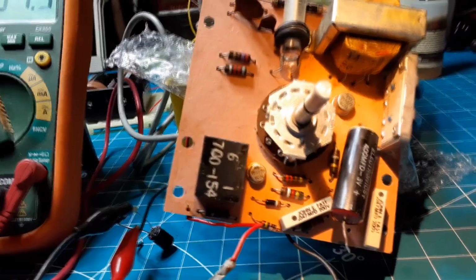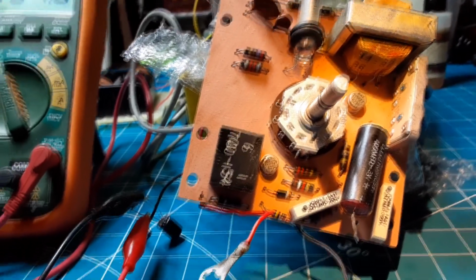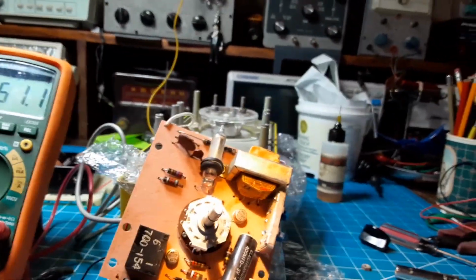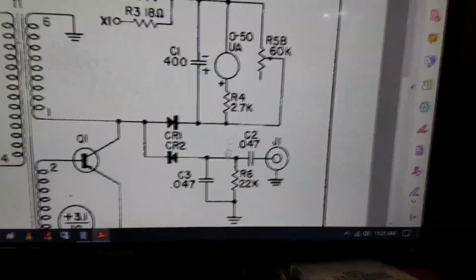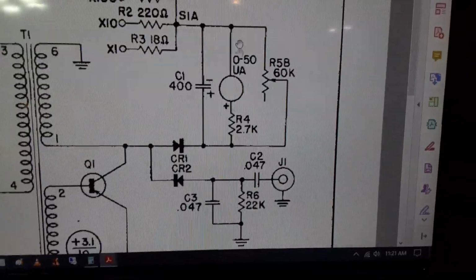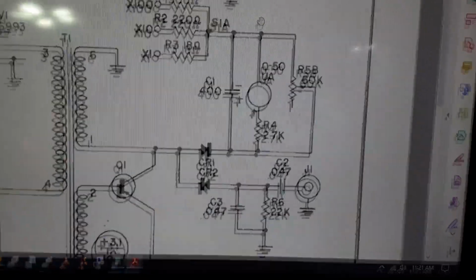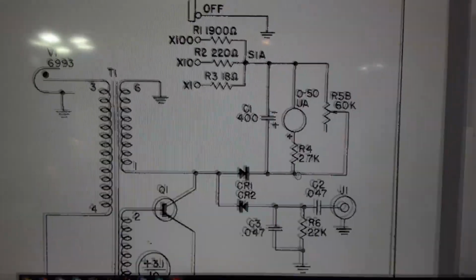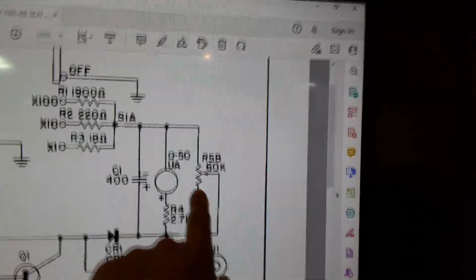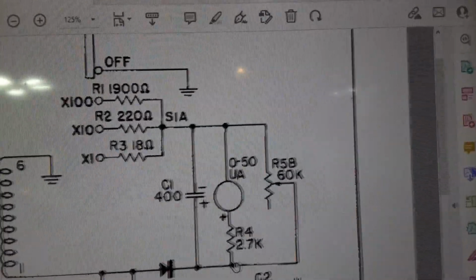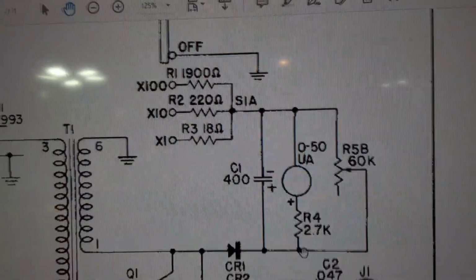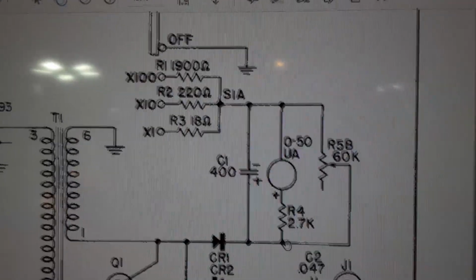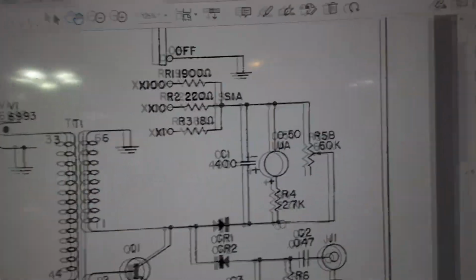And again, this is just the control for the switching. What did they call it? They called it an integration capacitor. And on the schematic, it's just this guy here, which maintains enough voltage for the meter. It just maintains a voltage across the meter, basically. And it's controlled by this resistor, so you even got more tolerance there to zero out the meter. That's all that's for, is to zero out the meter. So we're going to go ahead and use this one and take this one out.